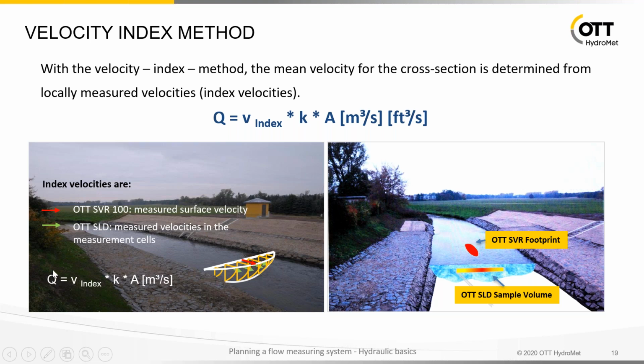Finally, remember the first equation we saw on the first slide: Q is V index, measured velocity, times correction factor, times cross-sectional area. The product of the index velocity and the correction factor is the average velocity in our cross-section. What we need to define is finally the K value. For this, we provide Protus2 software, which you can use to do the site calibrations. You can also do it on your own, and you can do calibration measurements in the field. You can compare the real existing average velocity from your calibration measurement with the measured velocity from your sensor. If you do this 5, 7, 10 times at different flow situations, you set up a velocity index rating.